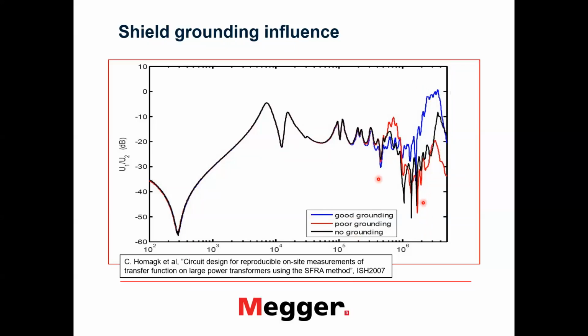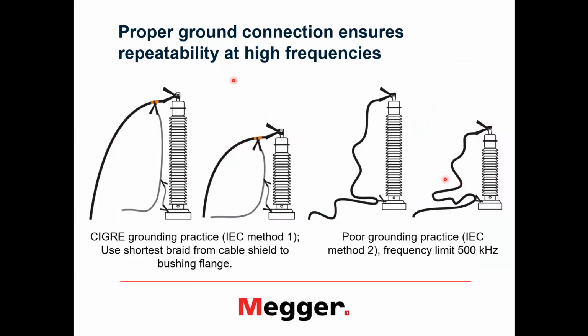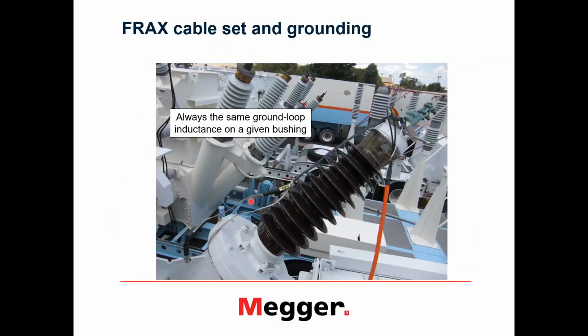So in this case, in the high frequency range, it would not be possible to make any conclusions whether it is a transformer problem inside or it is our setup. So I always advise to follow this practice: a short, straight line along the bushing surface, like in the picture here. We have a bushing which is sort of not vertical, and then the braid can come into touch with the bushing head. But for FRAX ground braids, we have rubber insulation on that, so it is not an issue. But you see the straight line down here to the ground point is connected.